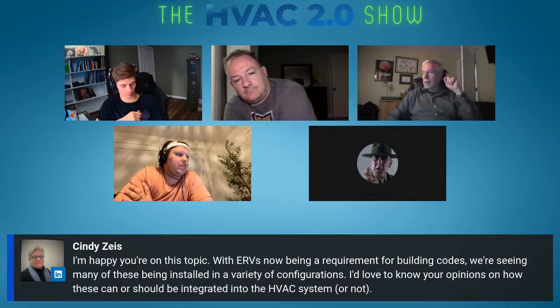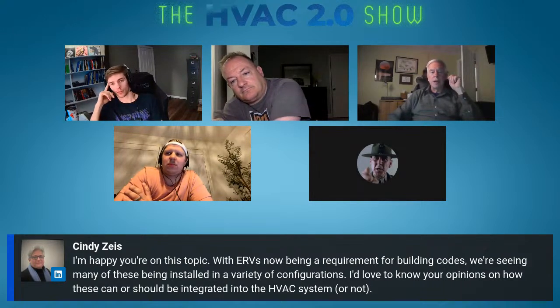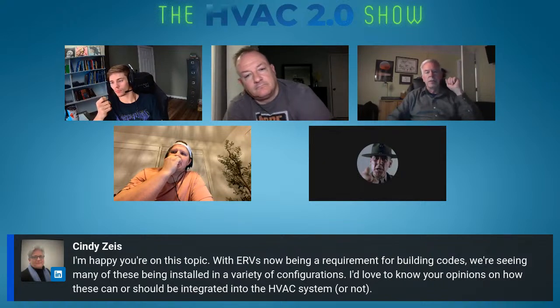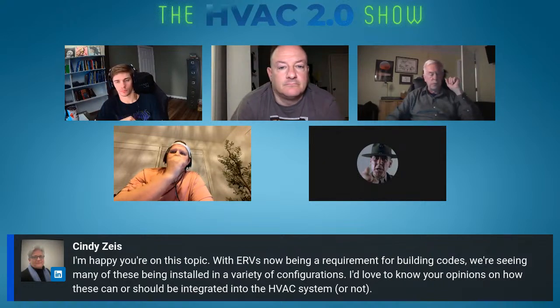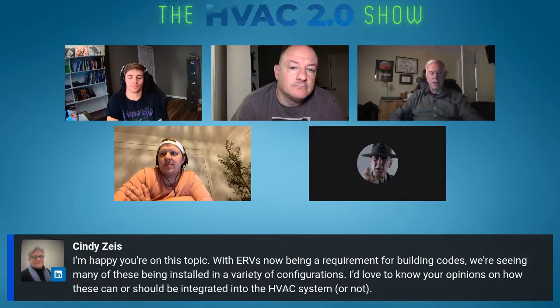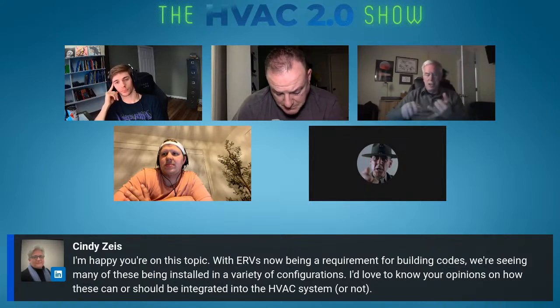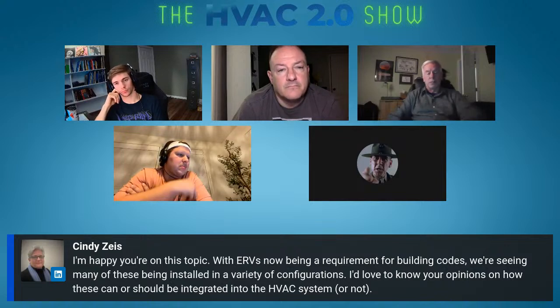I'd love to know your opinions on how these can or should be integrated into the HVAC system. So by and large, we're saying don't use them. Don't use them. And another aspect of it is that too often ERVs are not properly balanced. They're a whole other set of technical challenges that have to be addressed. You have to balance them and service them, which rarely happens. So you have a very expensive piece of equipment sitting there, either not working, harming conditions, or just being turned off.